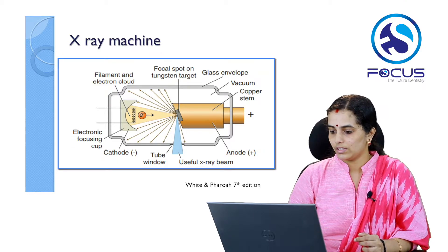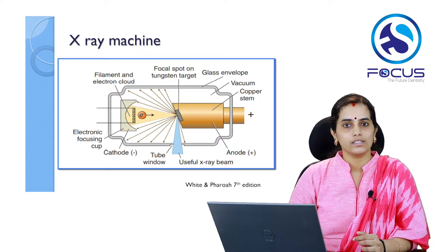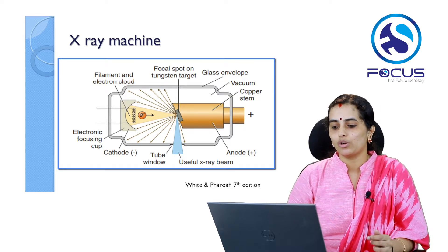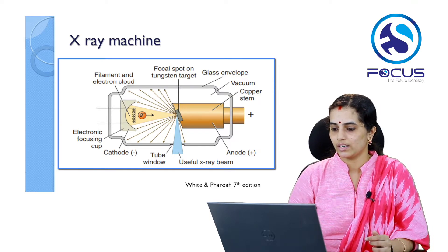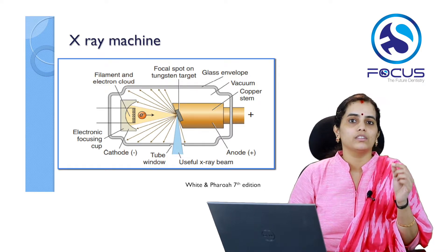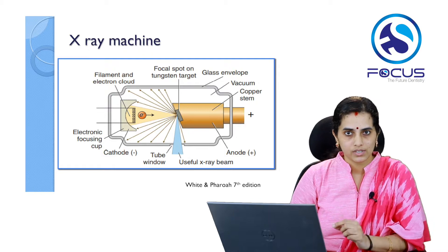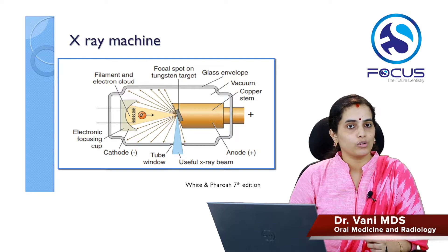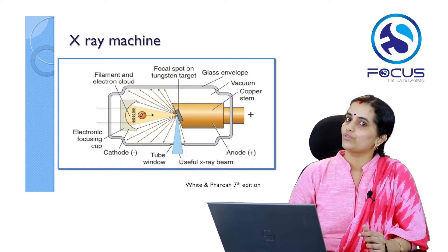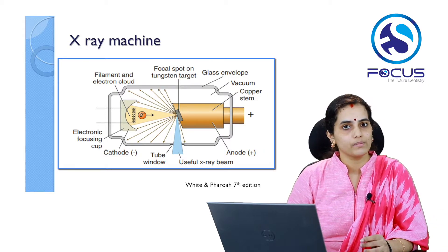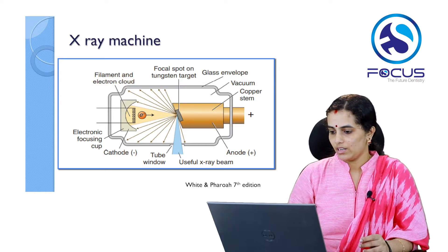The anode is positively charged and consists mainly of a rectangular-shaped tungsten target embedded onto a copper stem. The tungsten target is the area where the electron beam from the cathode strikes to produce X-rays. The point where the electron beam strikes is called the focal spot. The copper stem's role is to dissipate the heat generated at the focal spot.